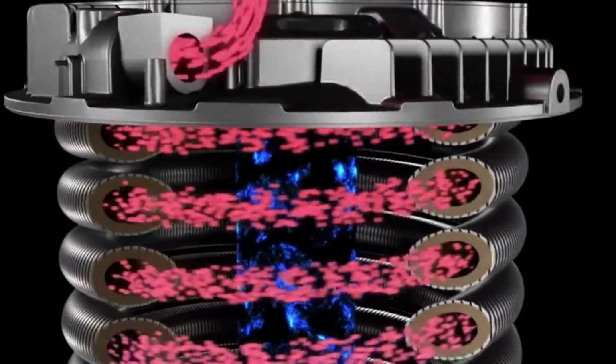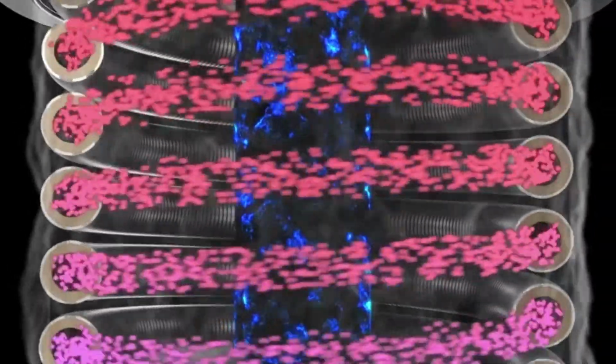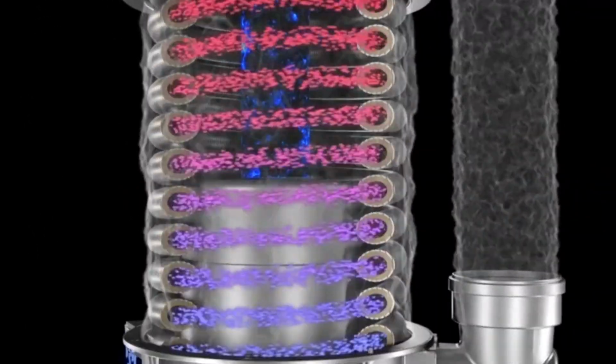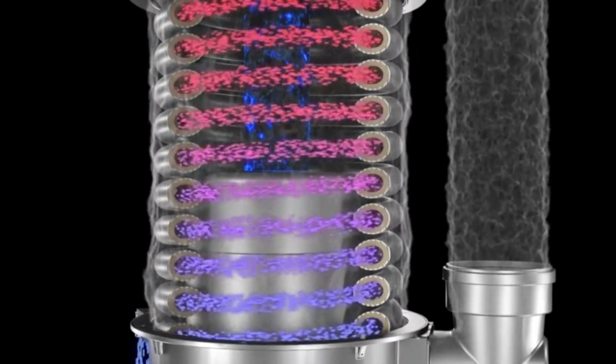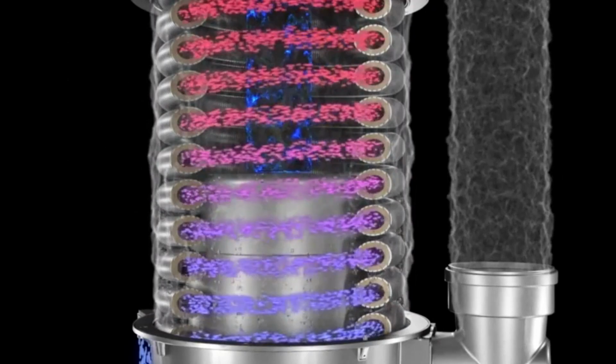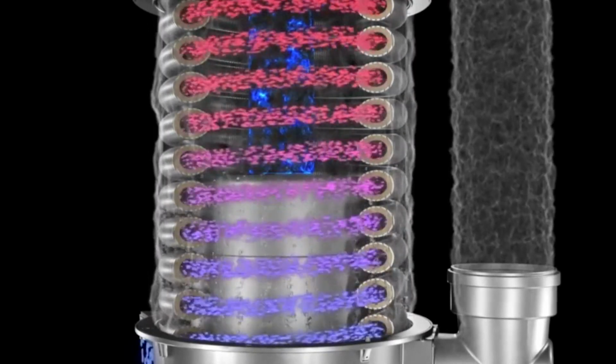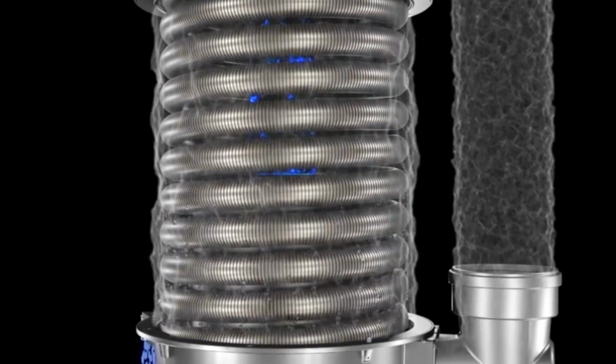top, ready for use. The modulating premix burner fires radially outwards to precisely match the load. Flue gases move downwards to the bottom casting while water flows up in the opposite direction, absorbing maximum heat along the way. By condensing the flue gases, an additional 12% heat is absorbed.